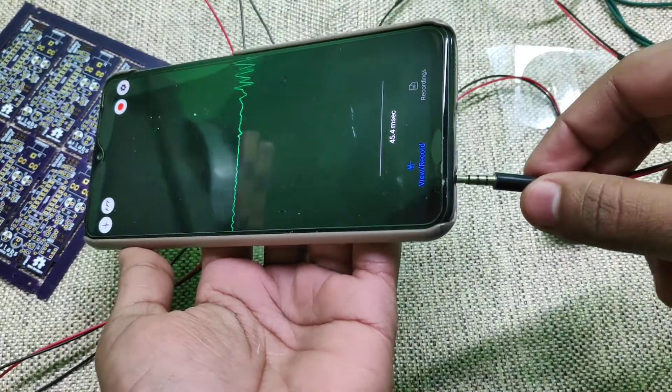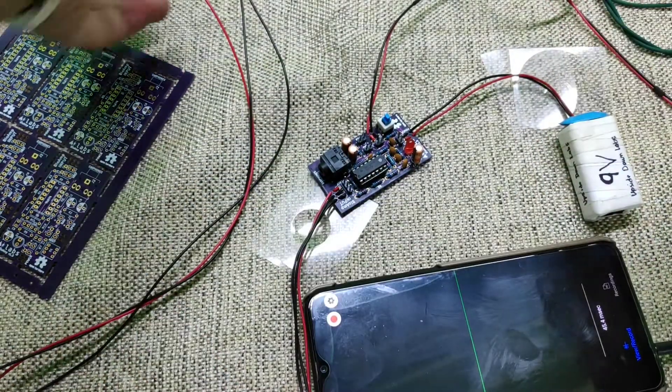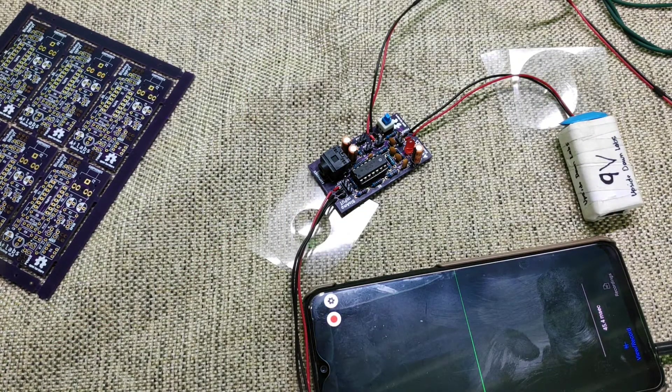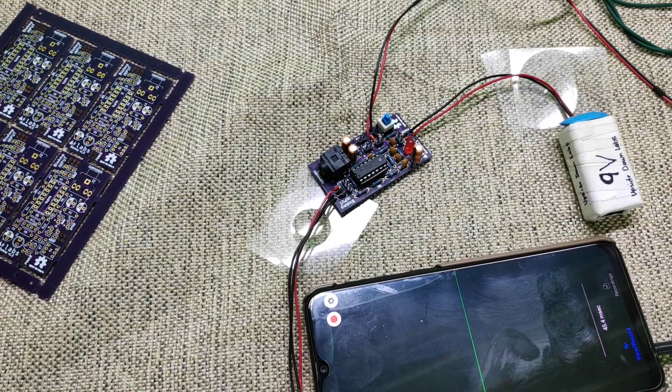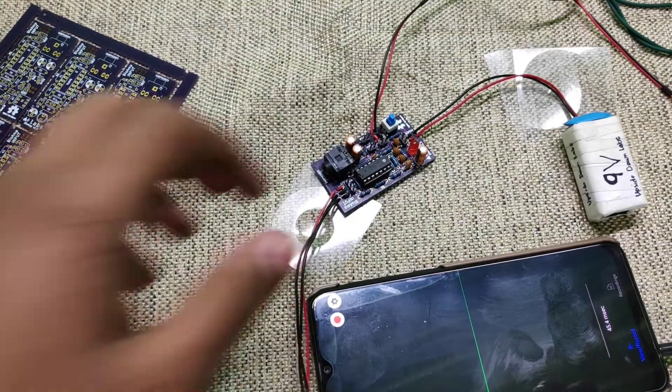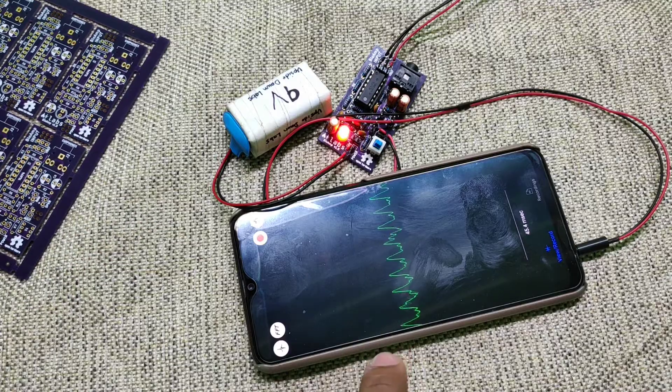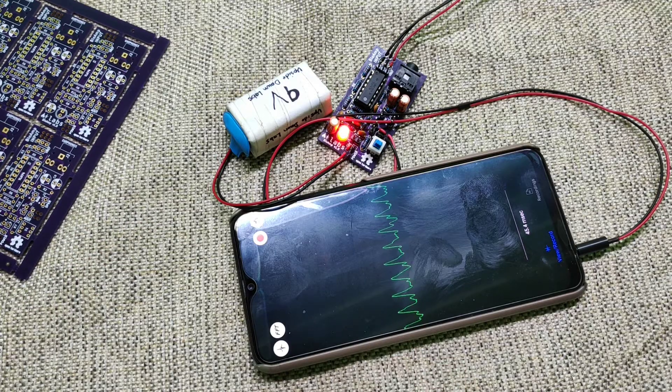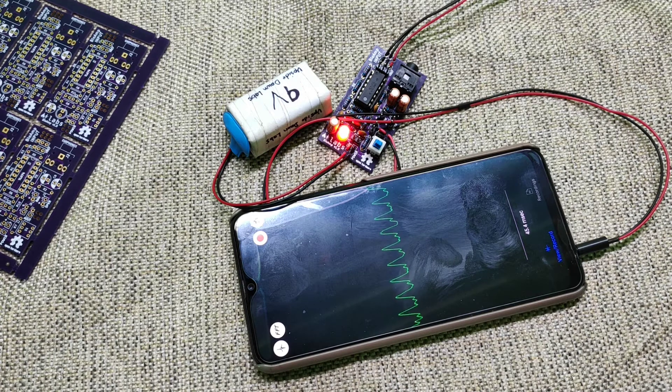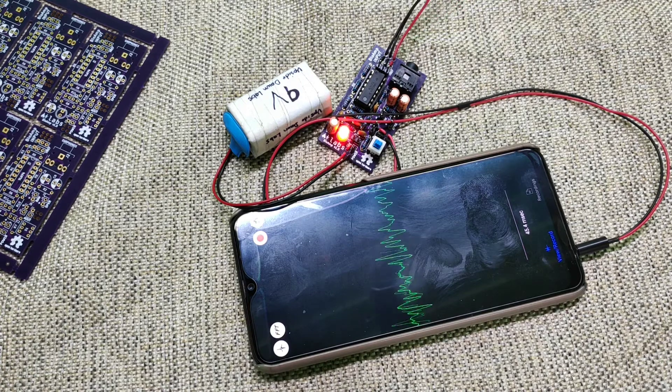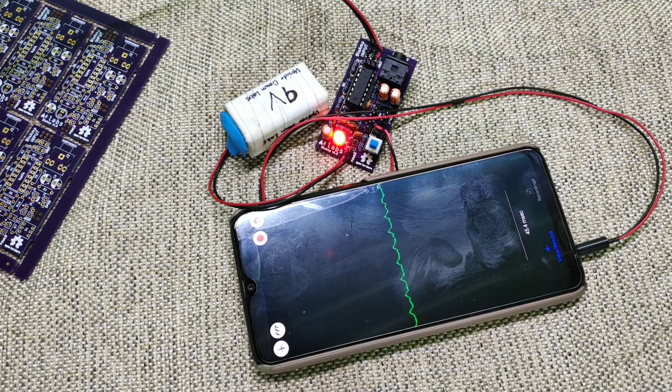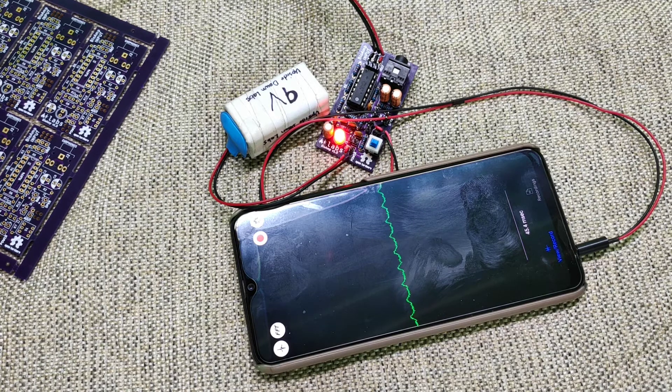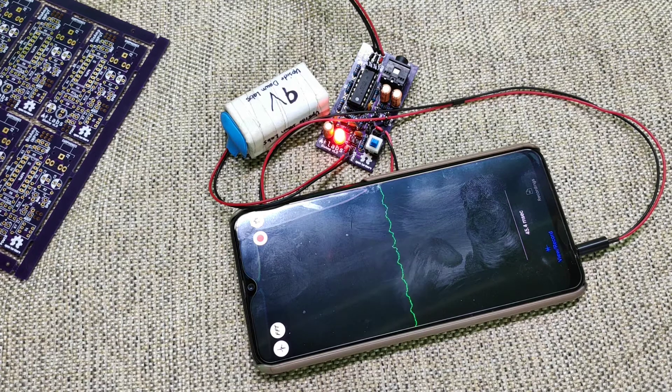Now plug this to the device and electrodes to the muscle, just like we discussed and turn on the device. This regular pattern which almost looks like a sine wave is a 50Hz noise. You are seeing this because I am standing very next to this AC main plug and when I take my hand away from the AC mains plug, you can see the signal is much weaker now.